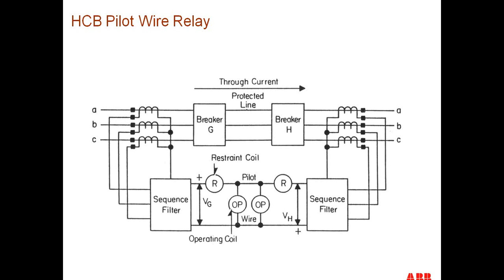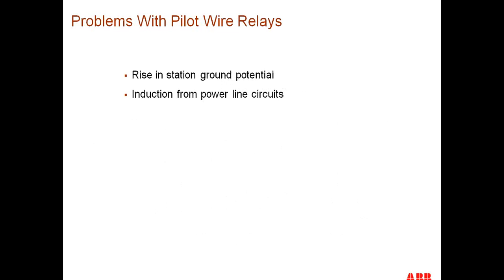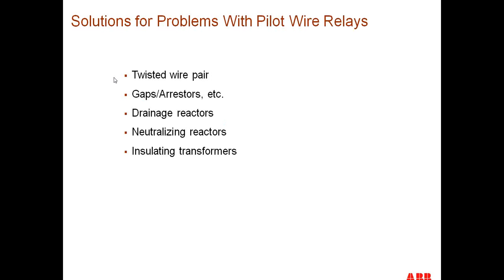So there are several things that were going against the use of this type of scheme, but two of those being the rise in station ground potential and induction of current into the twisted pair from the power line circuits. But over the years, several different remedies have come into play, using gaps and arresters across the twisted wire pair so we limit the amount of potential rise on either end, using drainage reactors, neutralizing reactors, and insulating transformers. Using this compendium of devices, we're able to get a pretty decent pilot wire HCB relay system.